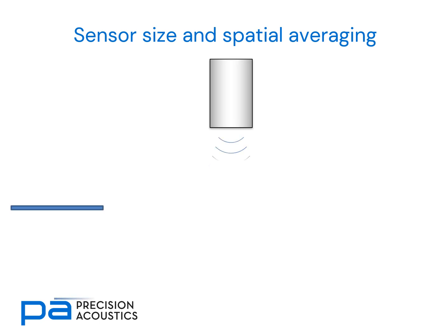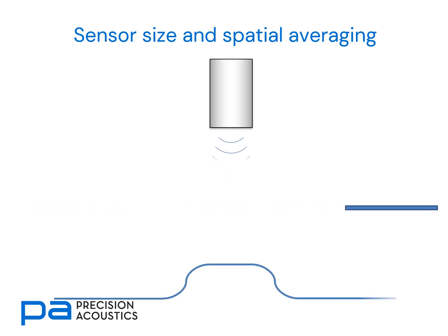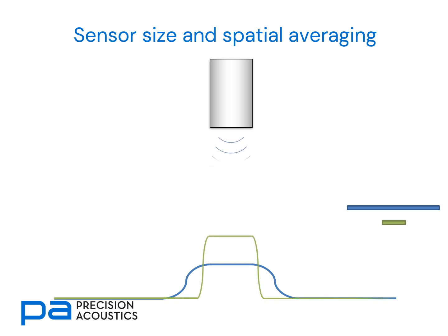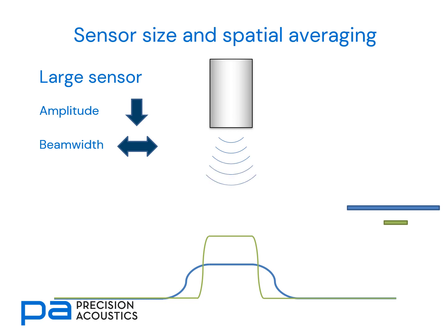Now let's consider the impact of sensor size and spatial averaging. Consider a source of ultrasound radiating forward. If we scan in front of that radiating source, we get a measured profile for the apparent beam width. If we undertake the same measurement with a very much smaller sensor, we find a very different profile. By using a sensor that's too large, we find reduced amplitude and an increased beam width relative to a very much smaller sensor.